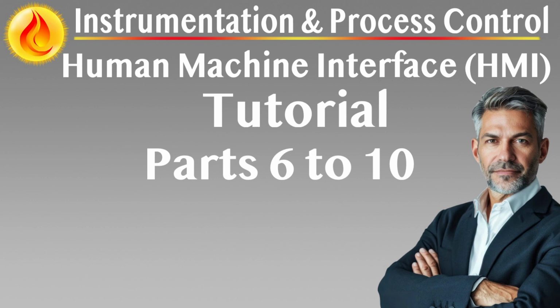During plant upsets or emergencies, a single operator should not be responsible for more than 3 active screens at once, e.g., an overview display, a detailed process graphic, and an alarm summary. This ensures manageable workload and focused attention.